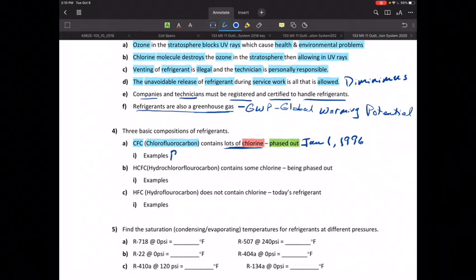So some examples. Whoops, I did not mean to say 22. That was a mistake. R11 is one of them. Refrigerant 11. Another one would be refrigerant 12. Now, refrigerant 11 is basically a low temp or low pressure refrigerant that we use in water chillers and a lot of large chillers. It's not a common refrigerant. We actually used to use R11 as a cleaning agent even in refrigerant lines, so it had a lot of really good uses, but it had a high concentration of chlorine in it compared to some of the other refrigerants. Refrigerant 12 was right along with it.